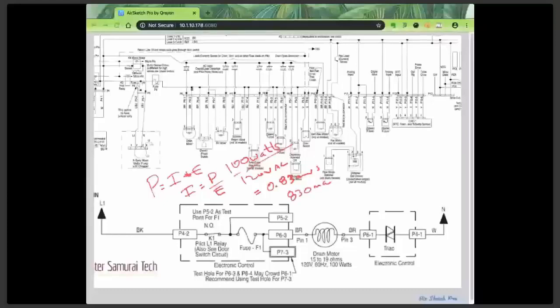And then I'm going to take my amp clamp. I'm going to energize the drain pump motor in self-test mode, put the clamp around here, and measure the amp draw on that drain pump motor. Much better test than just measuring the resistance of the windings. Now you're testing it as though it's really running, because it is really running, and you're testing it under run conditions.